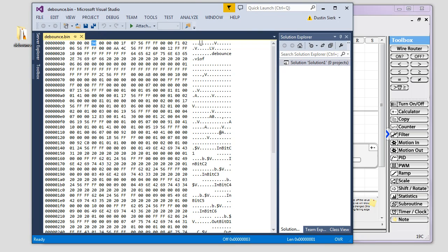So the first thing we do pertains to the Modbus address that we were dealing with. You need to know where that address is, because you might need to modify that for each PLC that you're sending it out. Maybe not, but perhaps you do. And if so, this is what's going to tell you where to change that address in the file itself. So you see right here, it's 4 bytes long, and at hexadecimal address 90, you'll find the Modbus address, and you see I programmed it for 7, and sure enough, there's a 7 there. So if you were to modify that to a 3 and then send all this code, you'd be telling that PLC, okay, your Modbus address 3, act accordingly.